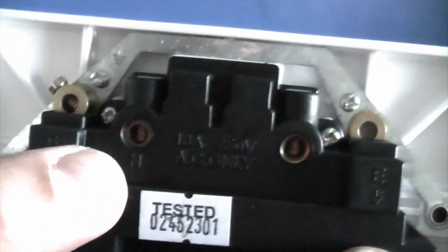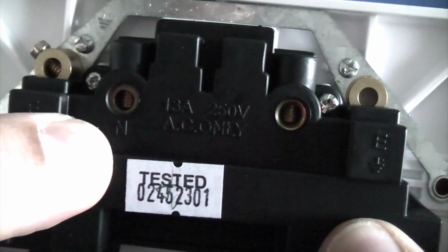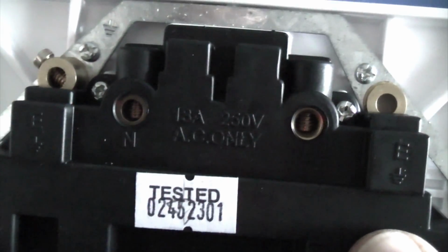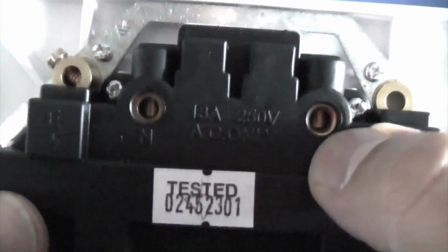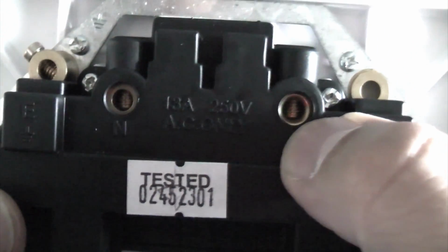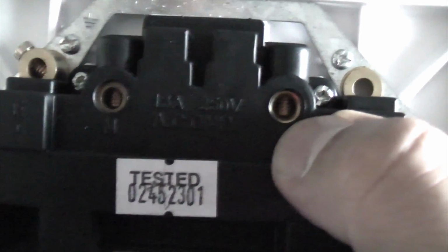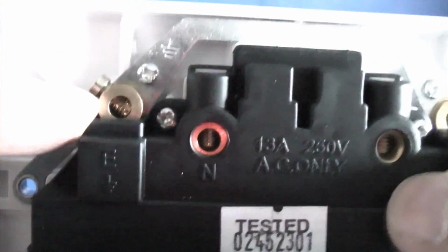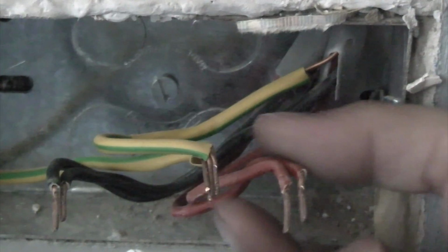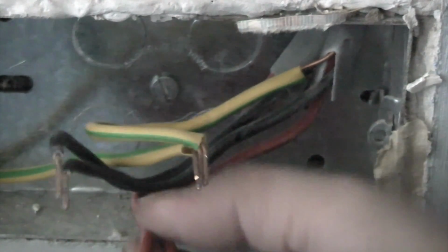So again, in the neutral goes the black wires, or if you've got a modern house, the blue wires, and in the live terminal goes the red wires, or in a modern house, the brown wires. And of course the earth goes into the earthing terminal. So before we put this back on, we need to move the 2 live wires over to that side and the 2 neutral wires over to this side.